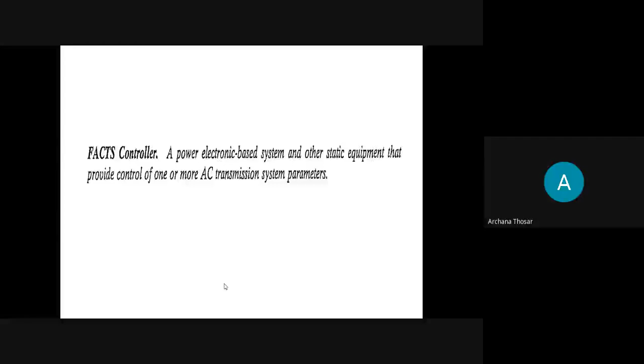So what are the parameters driving this change? I already explained that the line impedance is very important, and you can change it. When the angle is not large, control of X, or the angle, provides control of active power. Similarly, injecting a voltage in series with the line, perpendicular to the current flow, has an effect.